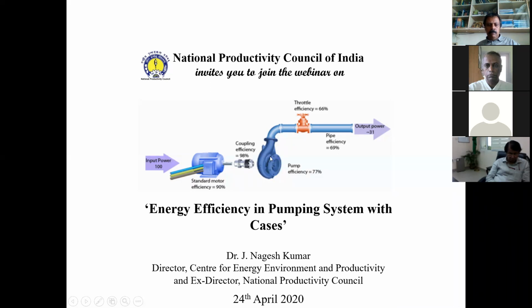The losses in the pump may range anywhere between, say, 25% to 50%, which means the efficiency of the pump itself is rather low compared to the efficiency of the motor. The efficiency of the pump, in normal practice, on average, could be around 65%. So about 35% of the power is lost in the pump itself, which is, of course, going off as heat. The amount of water that is going into the pump takes off this power as heat, and then it goes out along with the water. So when we talk about the efficiency, this is the pump efficiency, 65% as a percentage of input power. And then what happens here? Where the water is used, how much water should be used, at what pressure it needs to be used. All this will determine the overall efficiency of the system.